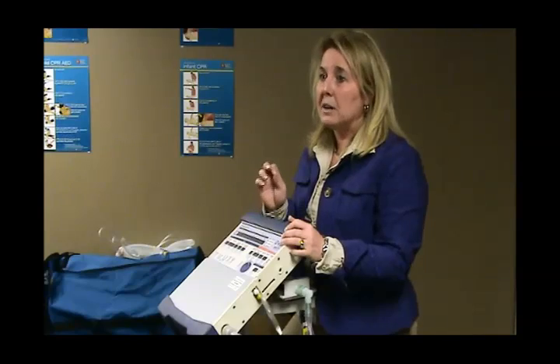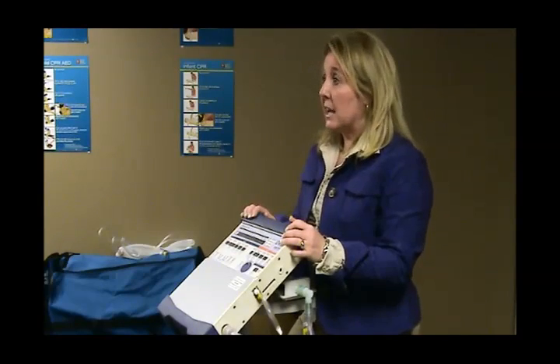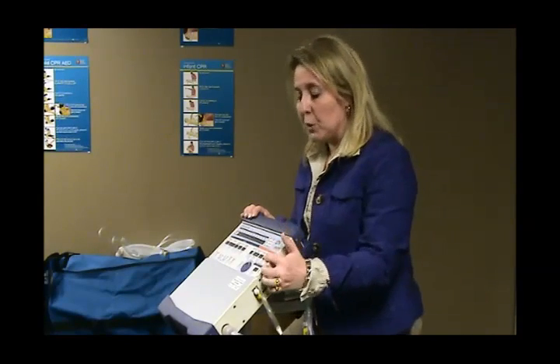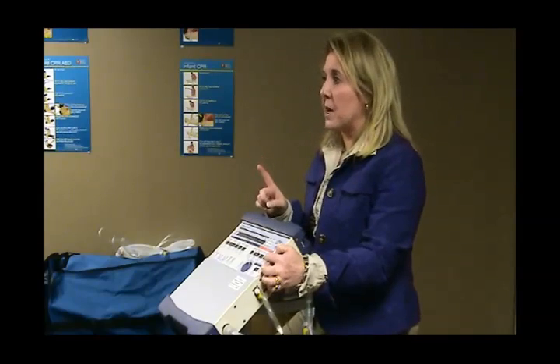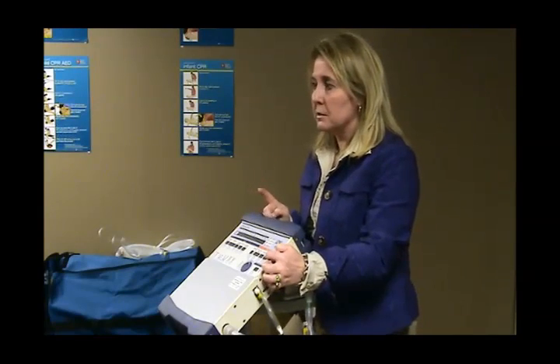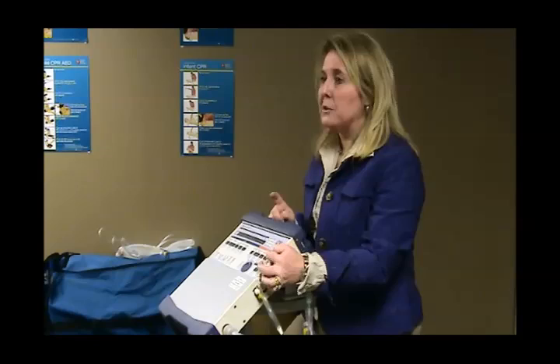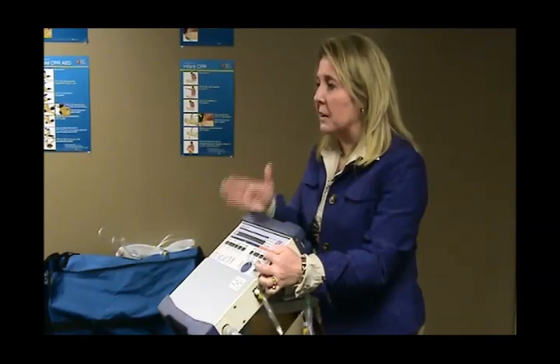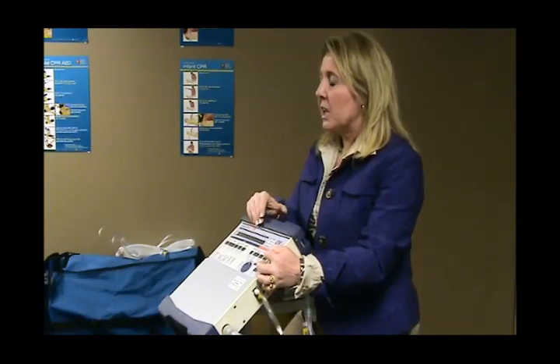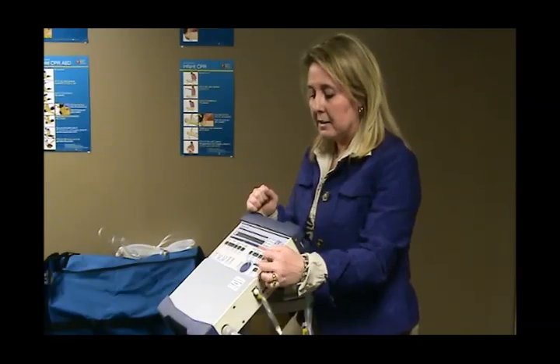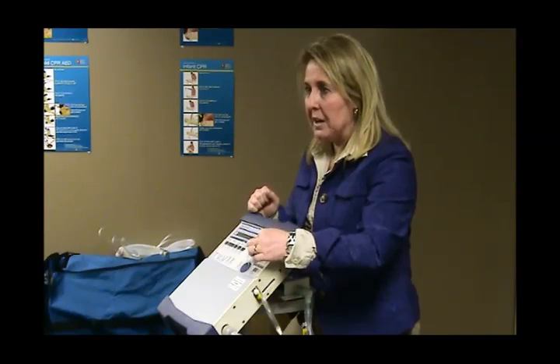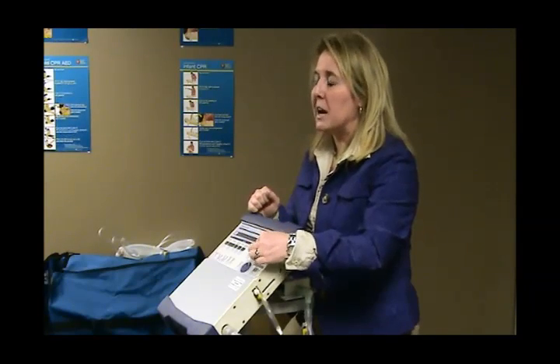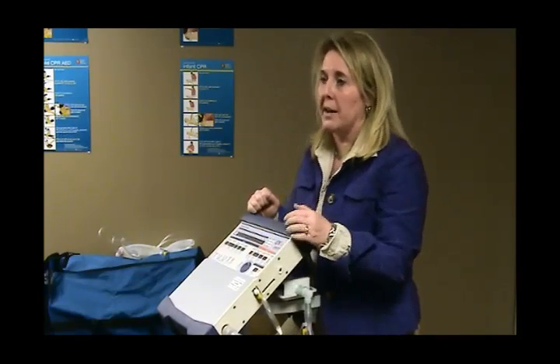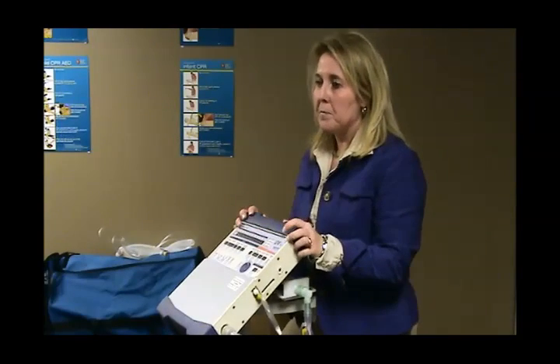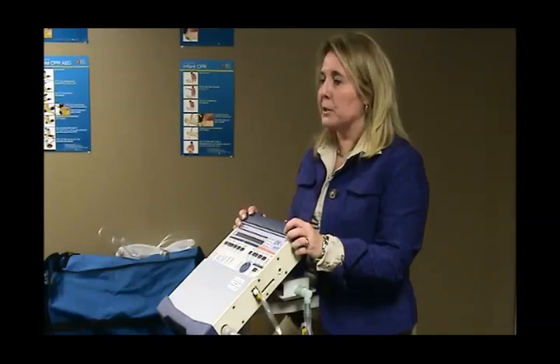Sometimes when patients have an intentional leak, like with a speaking valve, we do have to shut that off. I'm going to talk to you more about that when we talk about our 5 buttons, okay? But sometimes you will have to shut that off only when the speaking valve's in line. If we have somebody who's pressure ventilated, we should always have something, even if it's 0.1, on that low minute volume alarm. Just had a long talk with some folks about this, and we had a controversy back and forth about it.